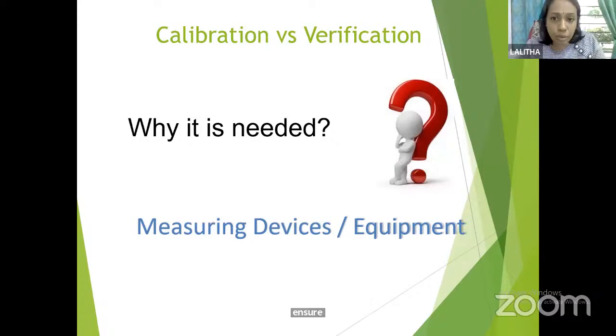Okay, calibration versus verification. Why is it needed? Why is it very important to have measuring devices and equipment in our labs? The first thing is that there are two main objectives for calibrating measuring devices and instruments. Firstly, calibration checks and verifies the accuracy of measuring devices. Secondly, calibration also creates traceability of the measurements to ensure they are consistent with other measurements, so that when we use the device, we don't make any mistake.